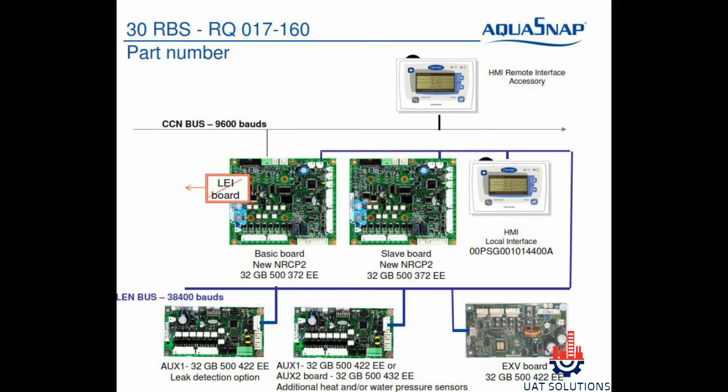HMI local interface is the display controller used to access the parameters and configuration. AUX boards are used for additional heating systems. The expansion valve board is used only in models from 039 to 160. All boards communicate to the main board via LEN bus, as the blue line is shown connecting all boards in the video.